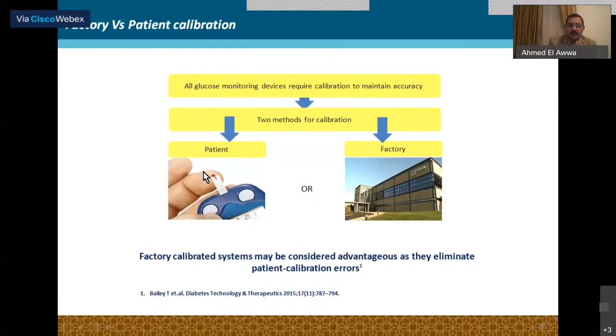There is one indicator used to evaluate the accuracy of the sensor, called MARD, mean absolute relative difference. This MARD means how much the sensor differs from the blood glucose measurements. What's accepted is for the difference to be less than 10% of the data.